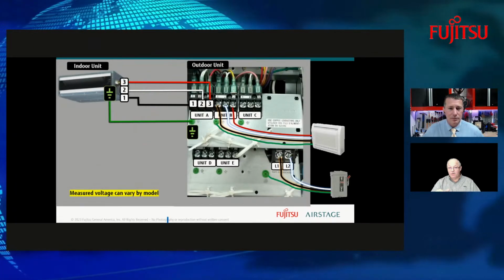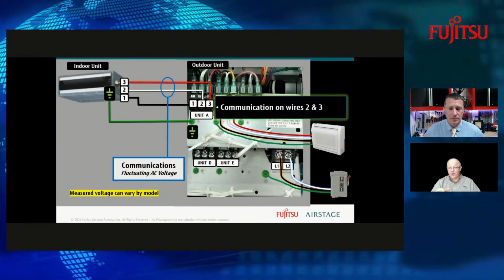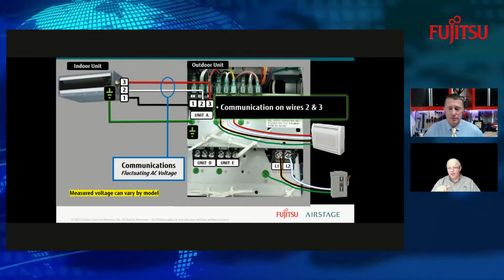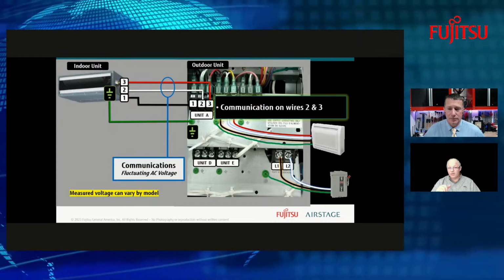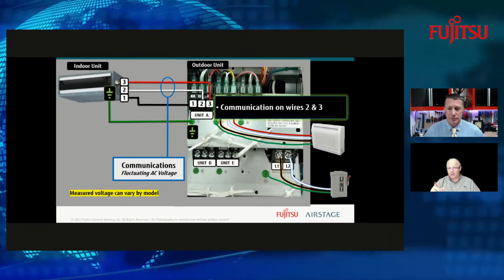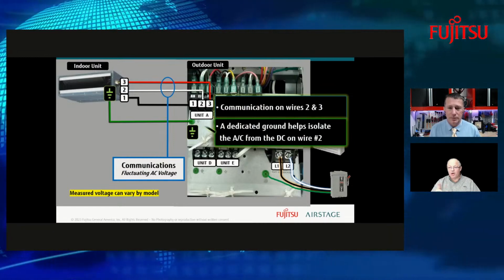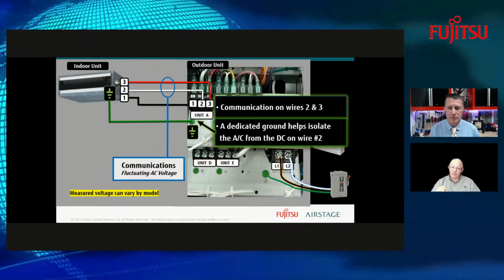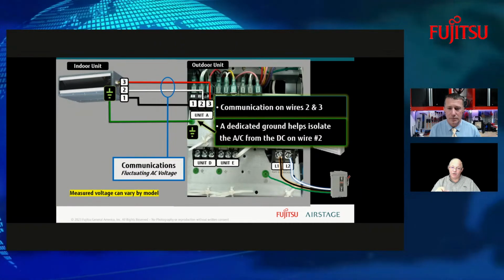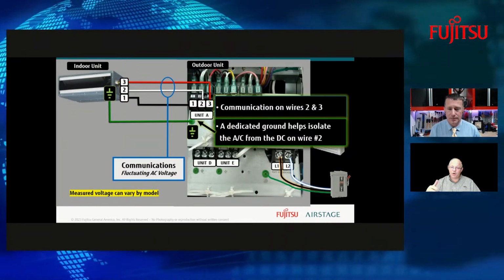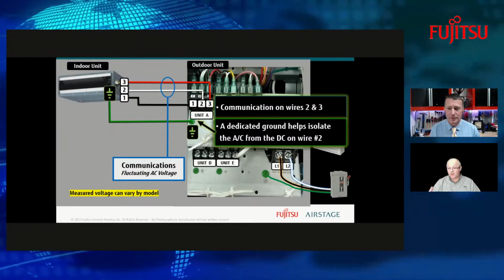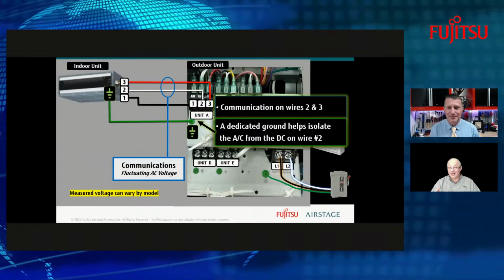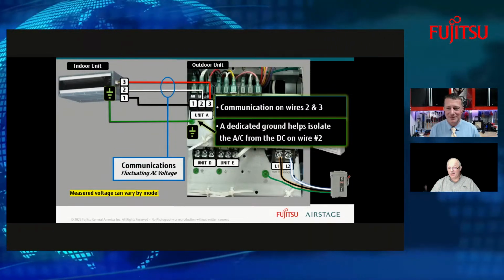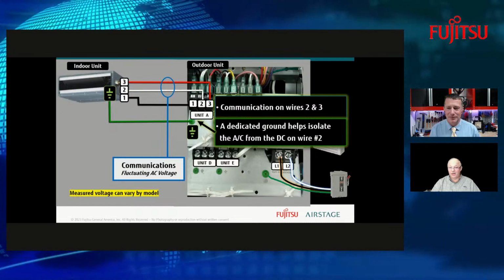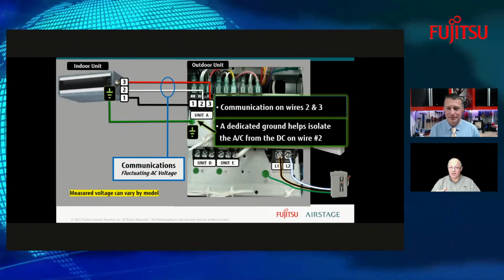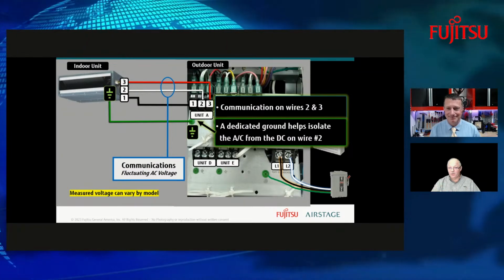All right, so if I go right here, you should see a fluctuating AC voltage on 2 and 3. This is the communication wires, where information is being handled both inside and outside. So they're both talking to each other. It's also critical to remember that if you don't connect this dedicated green ground wire, you could have some intermittent problems with the system, sometimes working, sometimes not. So one of the things we always look at is if someone says, hey, sometimes it works for a while and then it doesn't. The first thing our tech guys will ask you is how many wires are connected to the indoor unit.